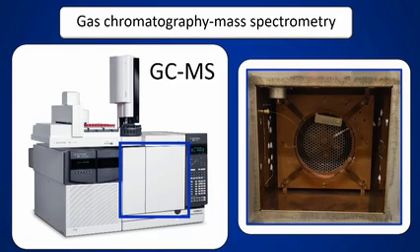This is sitting at 270 degrees, so all of our metabolites that are in liquid form will instantly volatilize into the gas phase, and helium will carry that onto this 40-meter long column that's only got a 0.25 millimeter core running through it. Coating that tube is a 0.25 micron hydrophobic sticky gum to which our molecules will attach.